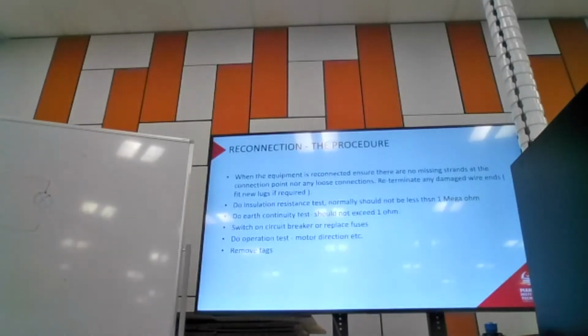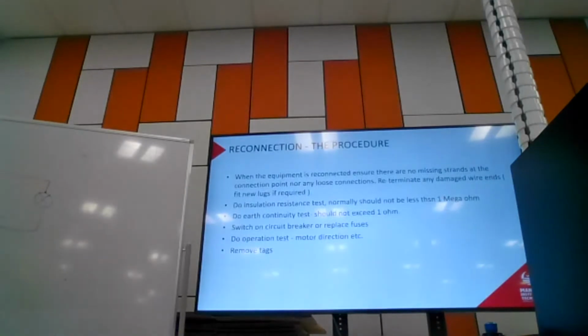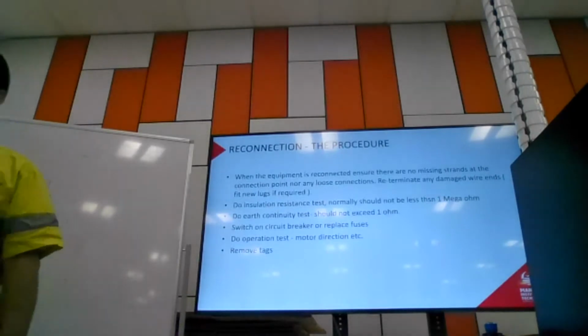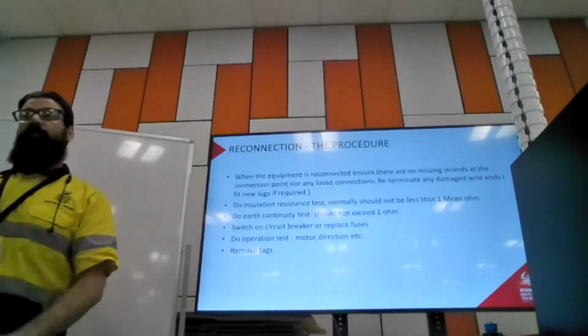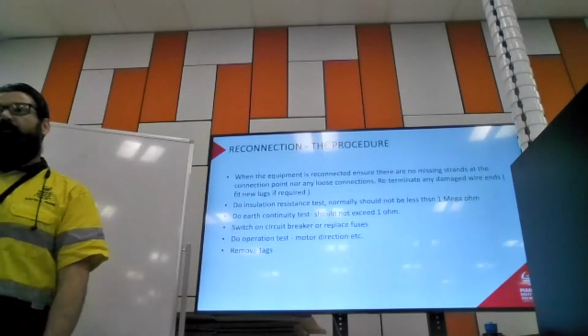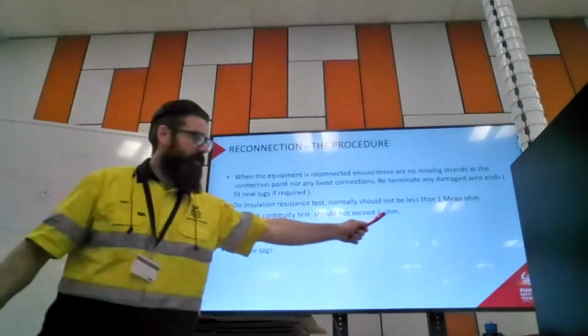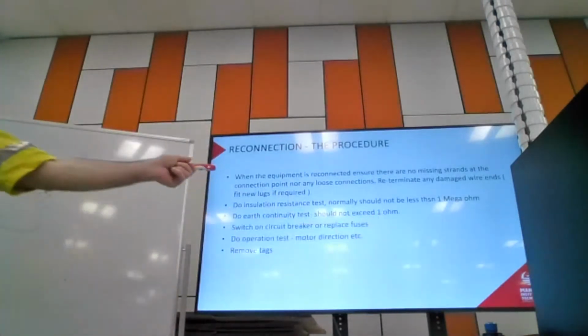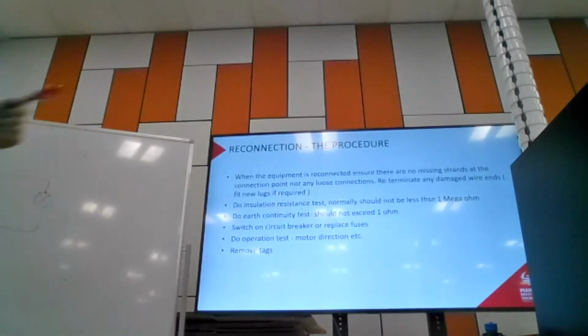It depends on the size of the circuit breaker and the size of the cable, which is in this table 8.1 in ASNZS 3000. It might be table 8.2, I can't remember. And ASNZS 3000 tells us what the earth continuity values for individual sub-circuits should be. But for an appliance, it's 1 ohm. Where do we find that information? Where would I get that reading from?